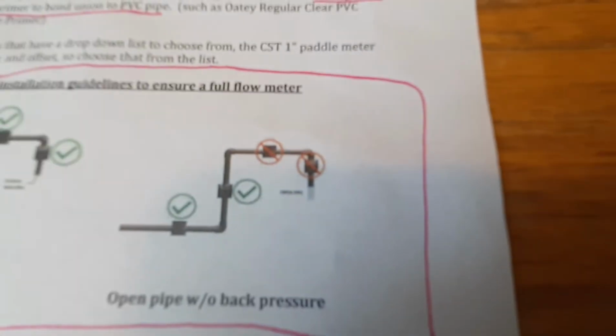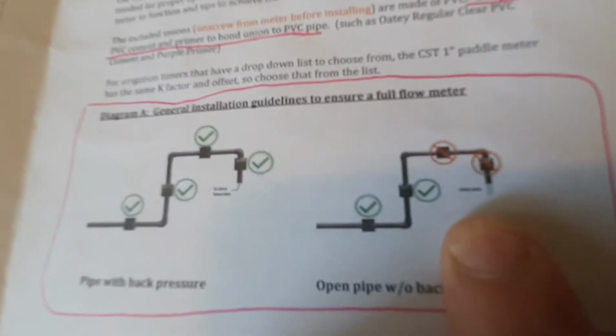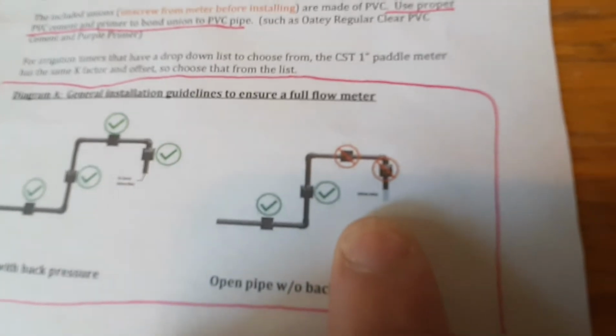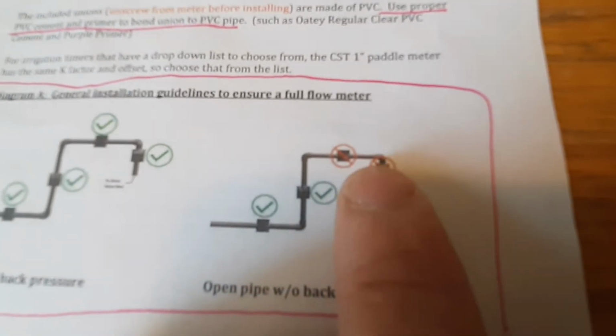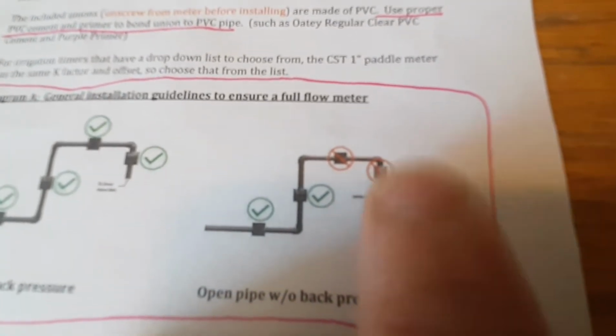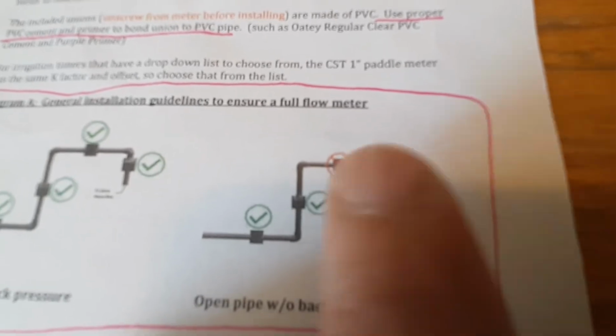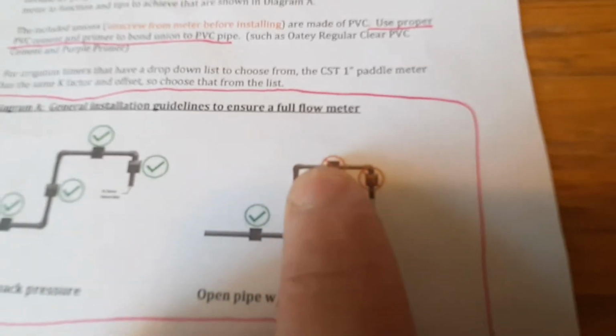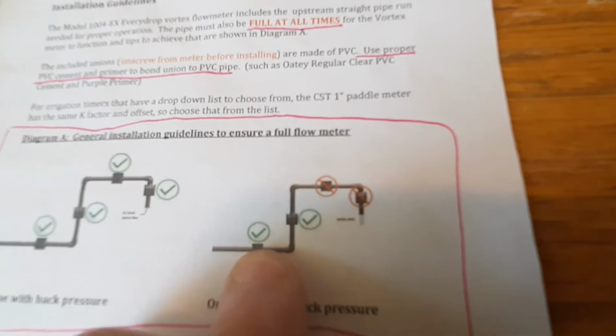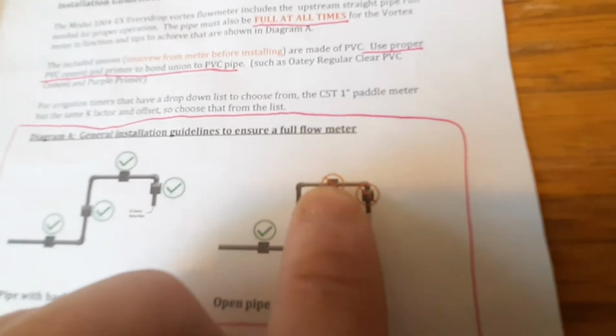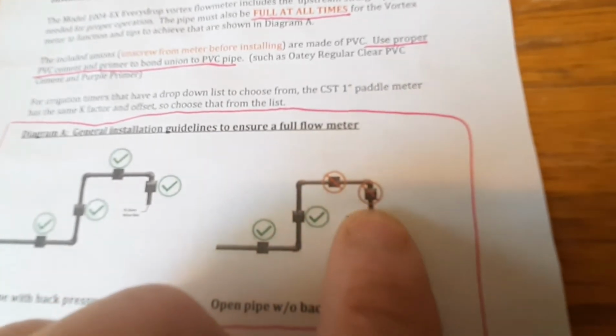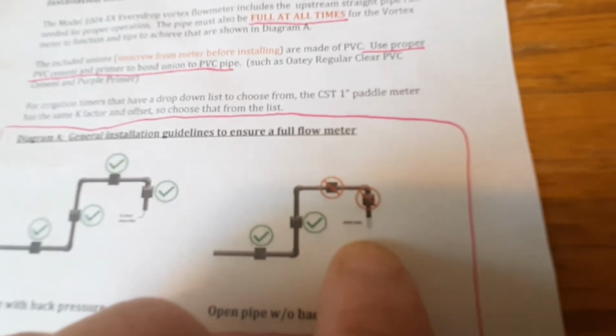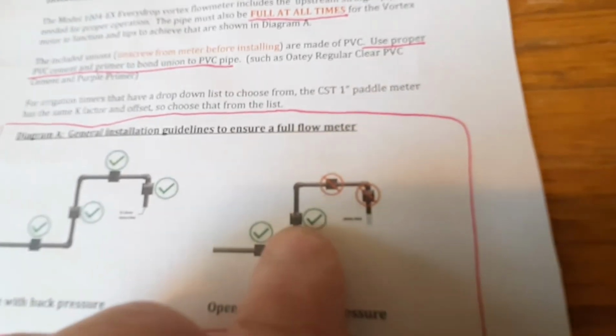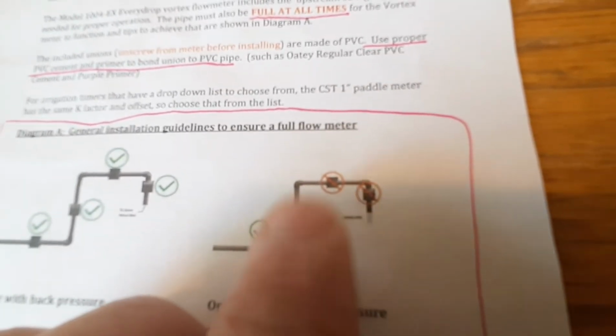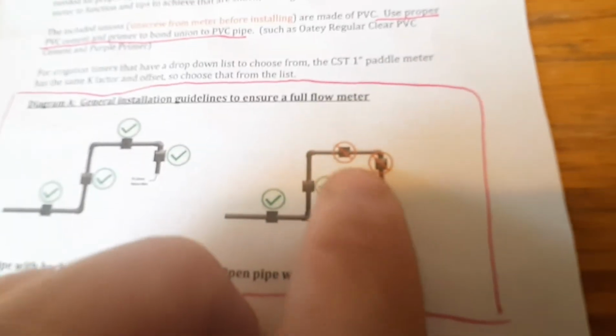What you cannot do, and I can't zoom into this little text, but I'll read it: it shows an open pipe with a spout. Basically what it means is, if you have a spout for whatever reason, you can't install it too close. The pipe will be full here and here, but if you get closer and closer, the discharge will prevent the pipe from being full, and the meter won't read correctly. So that's why you cannot install it that way.